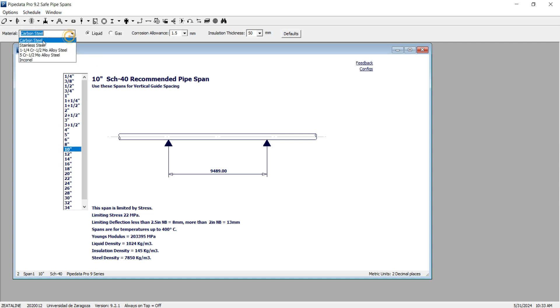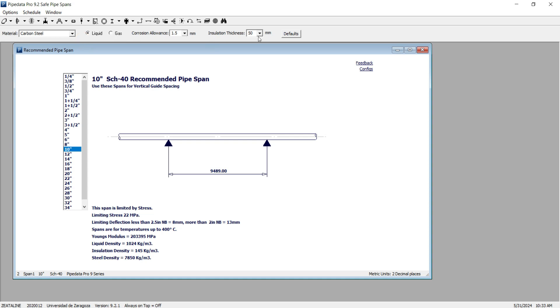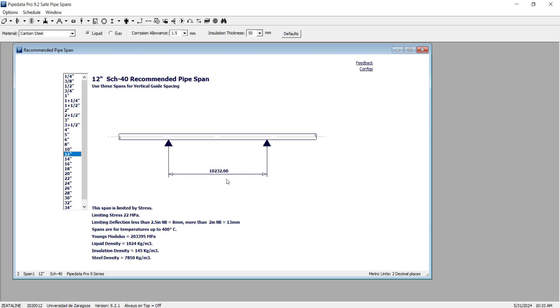Then you have to select the material, your service which is liquid or gas, the corrosion allowance, and the thickness of your insulation system. As you can see, these are all data that have effects on the weight of your piping system. Finally, by selecting the size of your pipe, you can see the maximum safe pipe span that you can have.